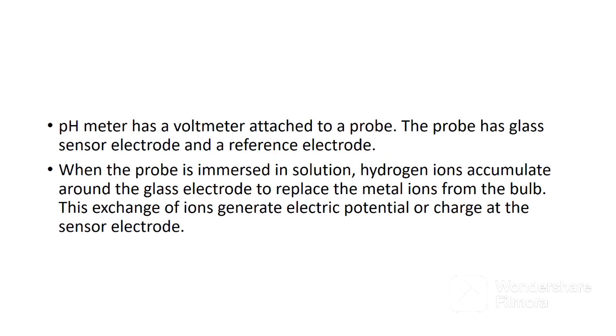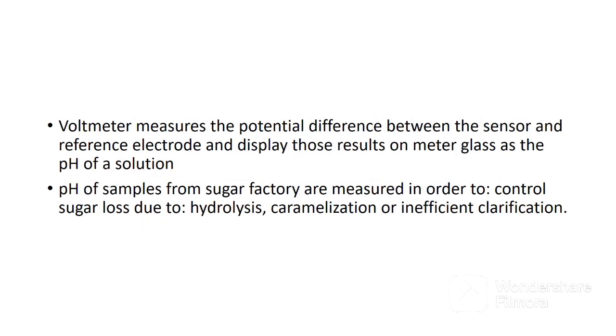The voltmeter measures the potential difference between the sensor and the reference electrode and displays those results on the meter glass as the pH of the solution. An increase in acidity of a solution means a greater concentration of hydrogen ions, which increases the voltage. This increased voltage decreases the pH reading in the pH meter, while an increase in alkalinity decreases the hydrogen ion concentration, hence reduces the voltage, leading to an increase in pH value on the voltmeter screen.